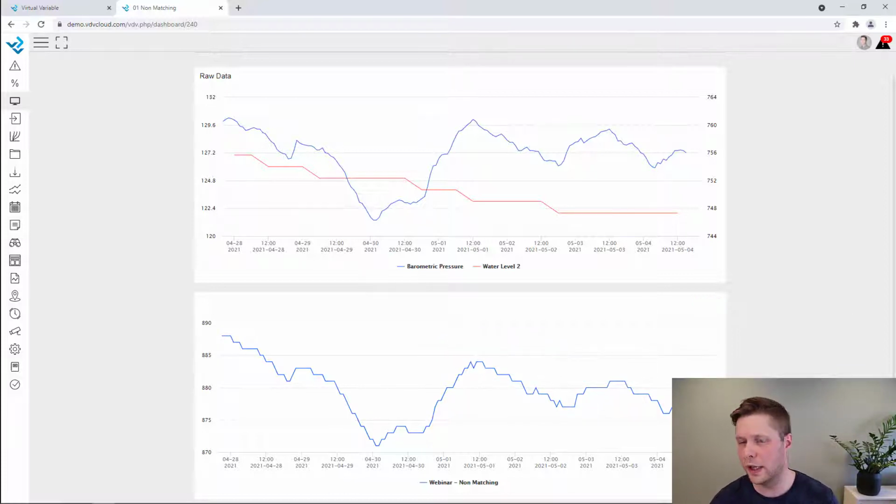Vista Data Vision is looking at exact seconds of the data. So if one data logger is drifting a little bit, the data is coming in at 5 seconds past or 10 seconds past or 2 minutes past, you can use this function to do the calculation and make sure you are aligning all of the data correctly and getting your corrected data onto the graph, onto the alarms.